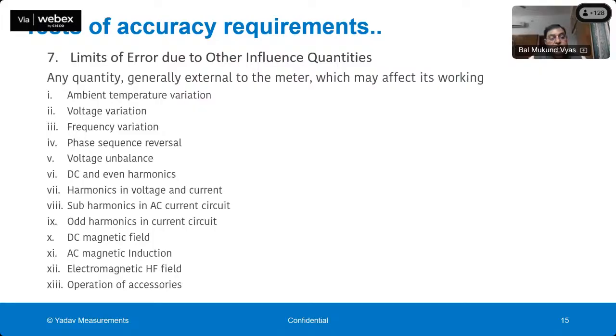Another influence is DC and even harmonics. When the meter is operating, we see that in our houses we use lots of electronic devices like laptop, TV, washing machine. All these devices do not have a perfectly 50 hertz load. They are operating on switch mode power supply or on diode based supply or on thyristor based, SCR based supply. Then they do not consume load with exactly 50 hertz. They generate currents with harmonics.